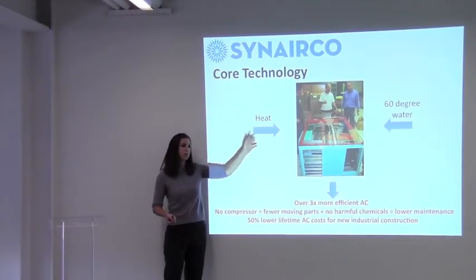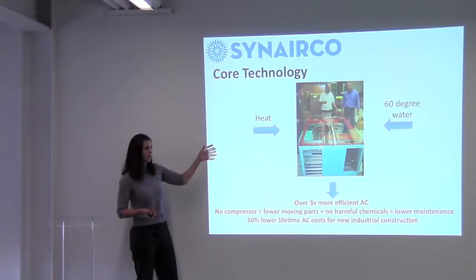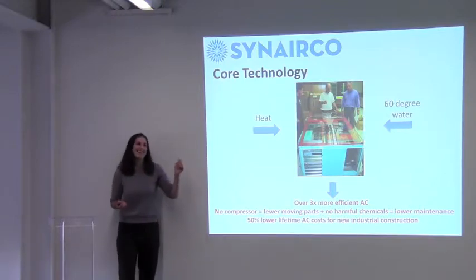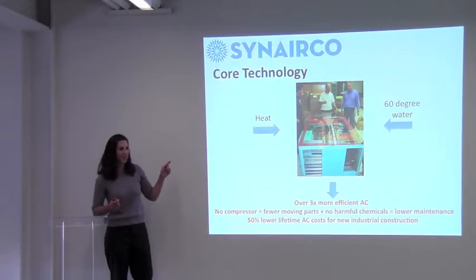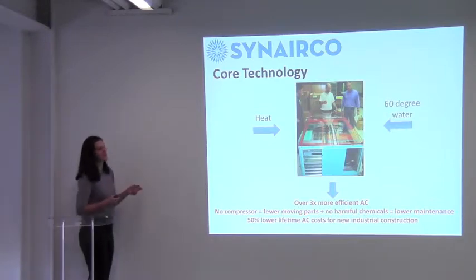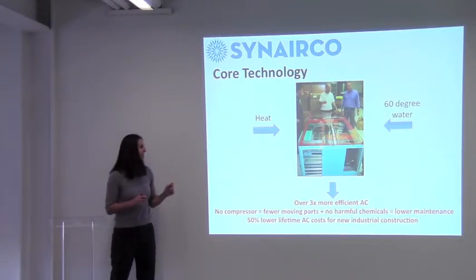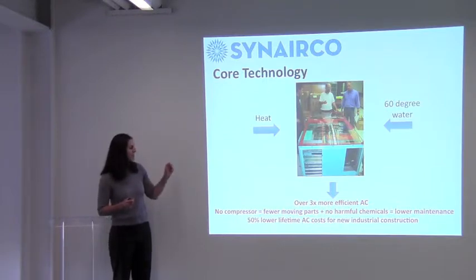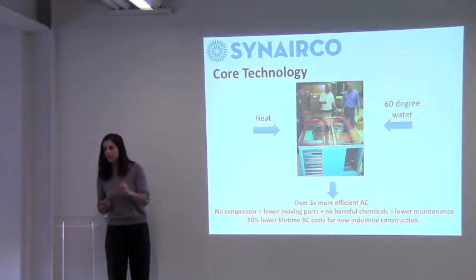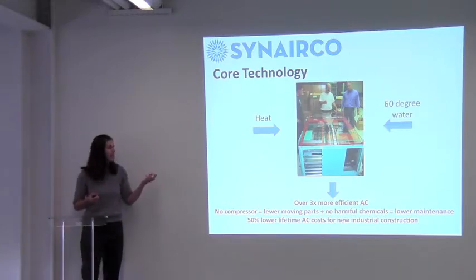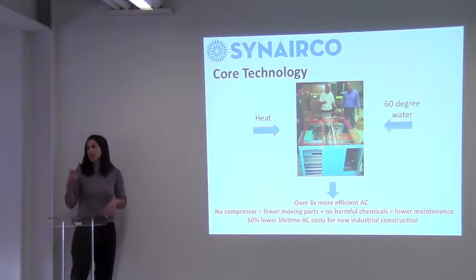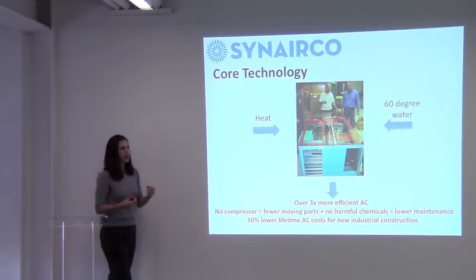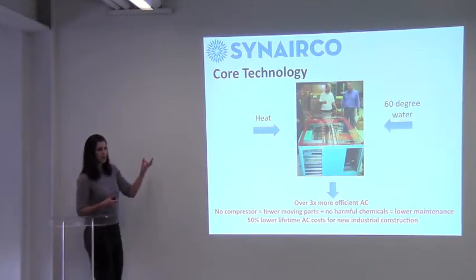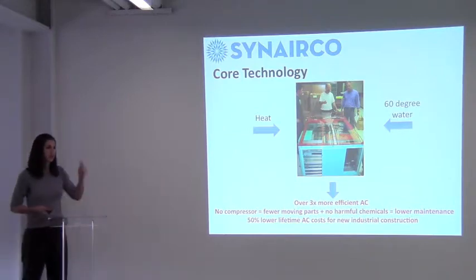So of course when we use this, we get our best efficiencies with a free source of heat. But I'm sorry, we used a boiler — we started with electric, but when Ian turned on the electric heaters, he blew up the unit. So we had to go back in and retrofit it with a hot water coil, buy a boiler, and run it that way. Actually, I was mistaken earlier — we used the cost of the boiler BTUs in our COP calculation. So that 1.8 COP figured on needing to pay for that heat. When you hook it up to solar heat or waste heat, that COP just drives straight up.